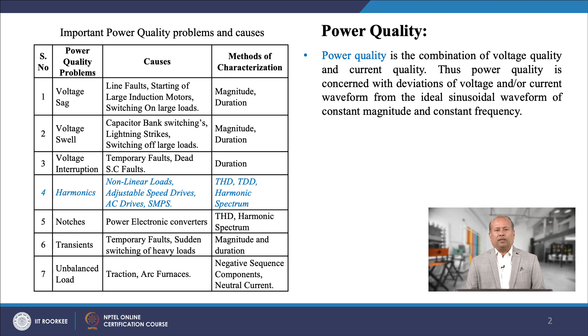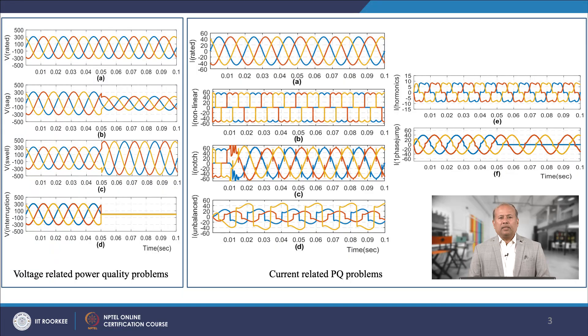Harmonic evaluation is done in terms of percentage of total harmonic distortion, that is percentage of THD. Theoretically, Fourier analysis is used to calculate the percentage of THD. However, practically we measure with a power quality analyzer and obtain the harmonic spectrum. Here in this slide we can see the power quality problem in graphical representation through simulated waveforms.